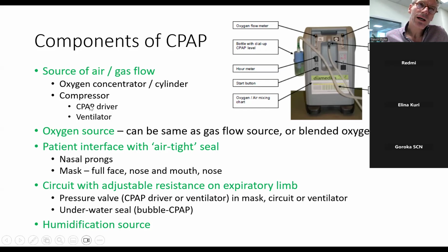There are other methods of gas flow production in other types of CPAP machines. You always need an oxygen source. I mean, in a CPAP machine, or almost always, and that can be an oxygen concentrator. Then the oxygen concentrator itself is the oxygen source. If you're using, say, a CPAP driver or a ventilator, then you need an additional source of oxygen. And so they're not as efficient because you often have to use high flow oxygen from another source, using a cylinder, and they can run out quite quickly. So the oxygen concentrators are much more efficient ways to deliver oxygen and air in a blended way to provide CPAP.